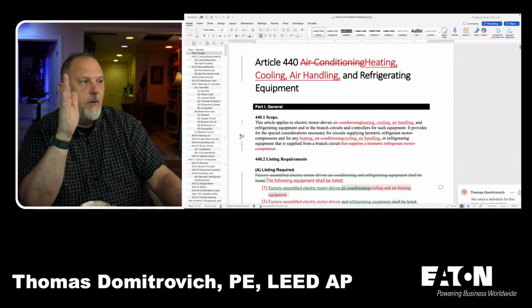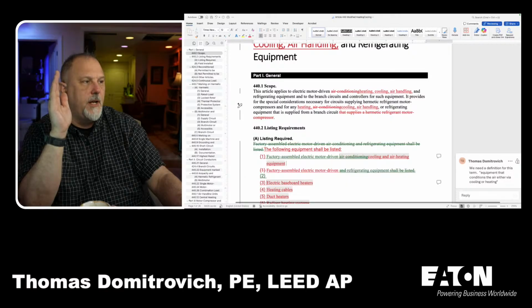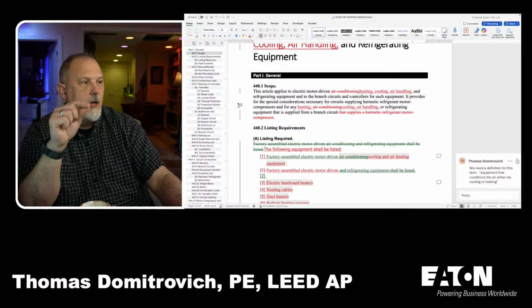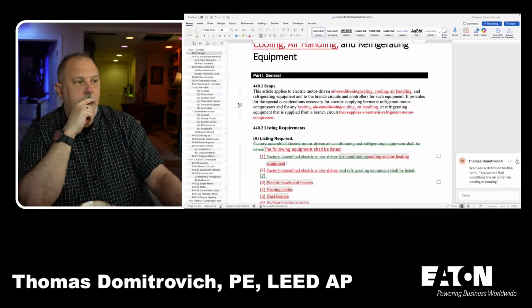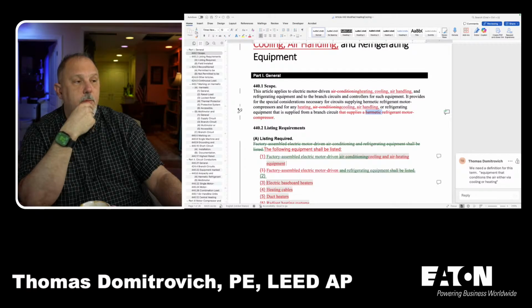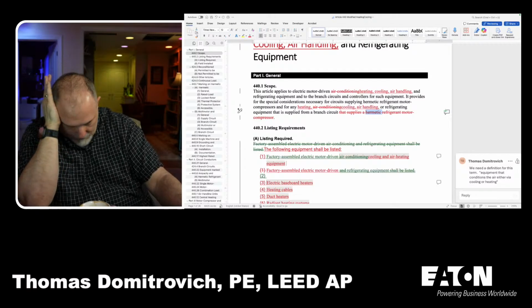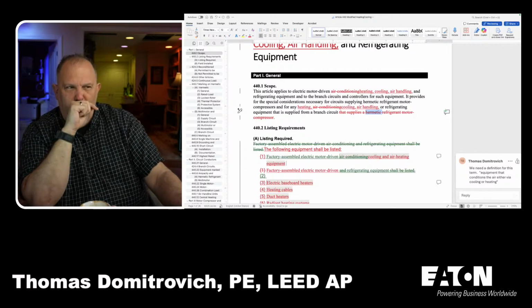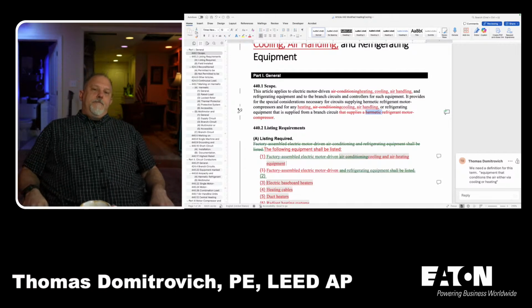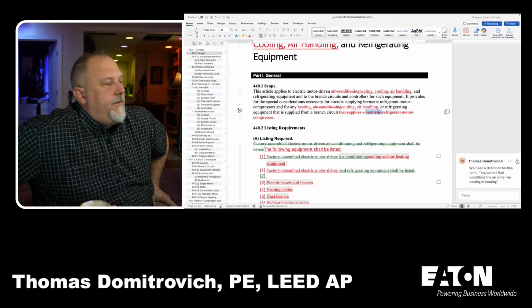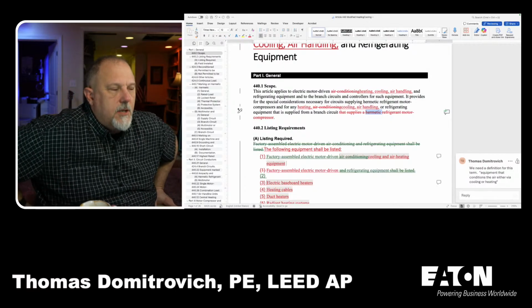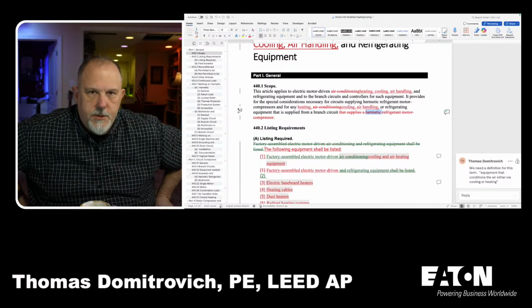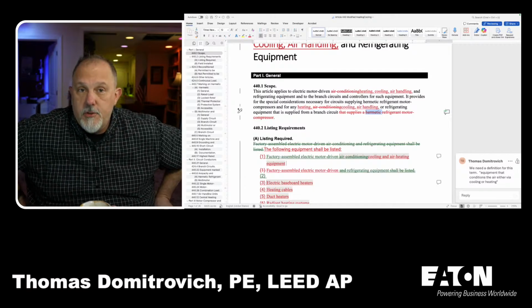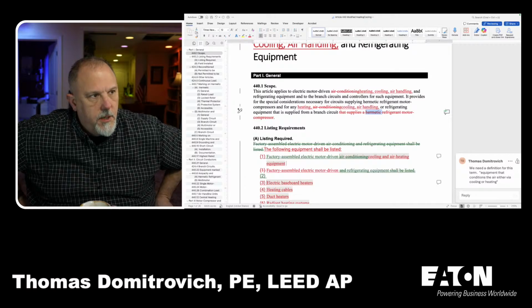All right. And what we did was we have 440, heating, cooling, air handling, and refrigerating equipment. It provides for special considerations necessary for circuits supplying hermetic refrigerant motor compressors and for any heating, cooling, air handling, or refrigerating equipment that is supplied from a branch circuit. Boom. Now, they had on here hermetic refrigerant motor compressors. Remember what 440 is about, because with hermetic refrigerant motor compressors, the motor is in a refrigerant. Because of that, it gets cooled, and they treat it separately.